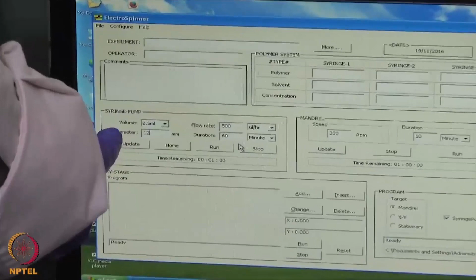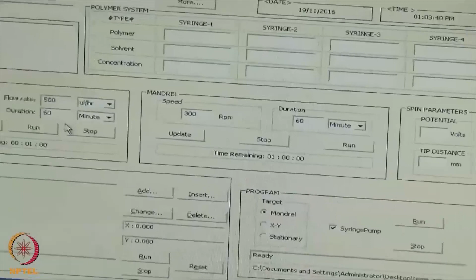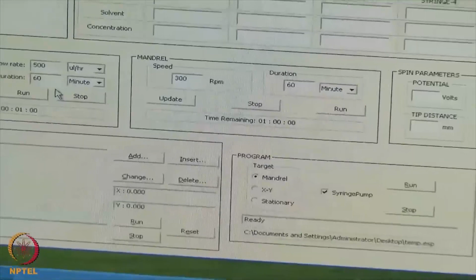There is a control software here which controls the electrospin unit. Several parameters can be controlled here. For example, the volume of the liquid polymer solution you have taken is given here, the flow rate at which the polymer solution is coming out of the needle is adjusted here, the diameter of the syringe, and the duration, how long you want to run it. So this is a flat plate. In case you have a plate which is rotating, it's called a rotating mandrel, we can set the speed of the rotating mandrel also here, and we can also tell how long we want to run this electrospinning unit by setting it here.